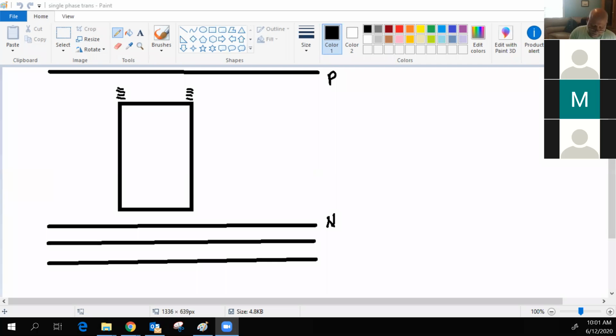We're going to start on the primary side, and we're just going to keep it just like what we're working out in the field. You're going to start off on this side. You can see P on here, right here. P designates primary, N designates neutral, and these will be your voltage wires here and here. And when we get into transformer banking itself, we'll actually change this up a little bit, not to confuse anybody, but we'll actually put the neutral down on the bottom when we start banking.